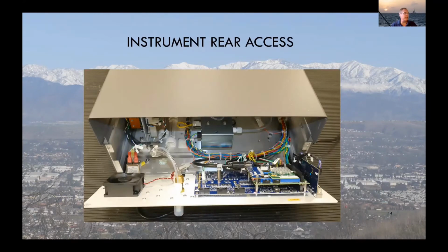Same thing in the back of the instrument. The rear can be pulled down and you can get access to the cooling fan, inlets, exhausts, and communication boards back here.